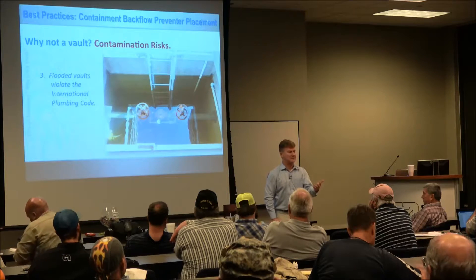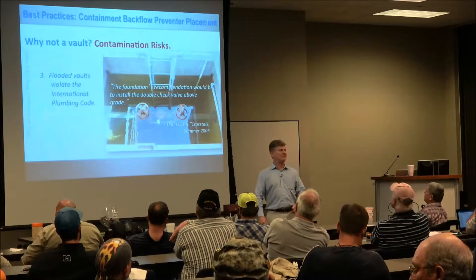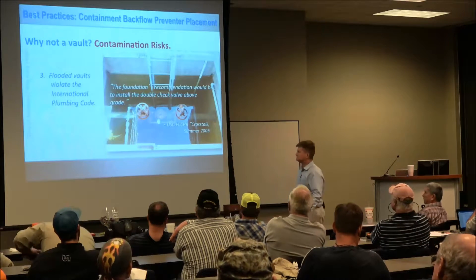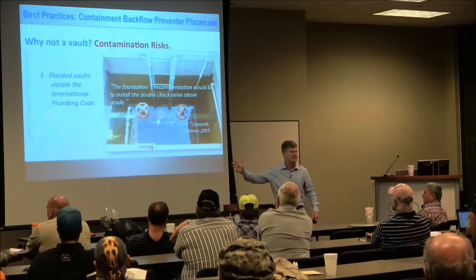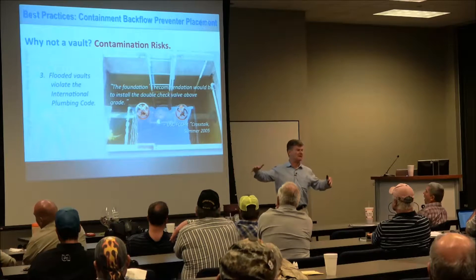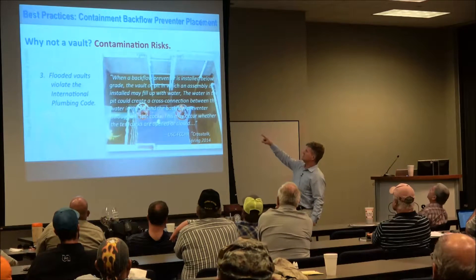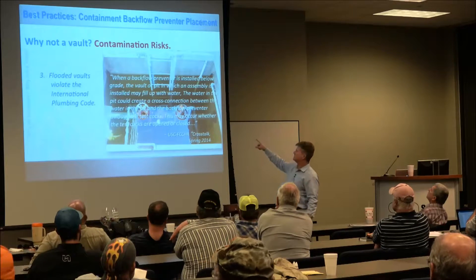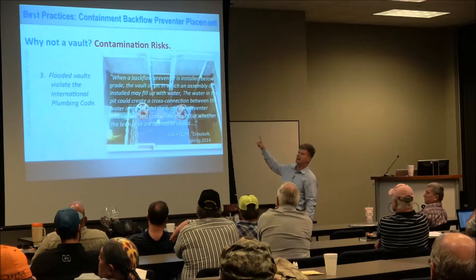We've already violated IPC in the way I look at it. Back in 2005, USC was the first to say the foundation's recommendation would be to install the double-check valve above grade. Being unsatisfied with the degree to which that advice was adopted, they published stronger language a couple of summers ago, saying: when a backflow preventer is installed below grade, the vault may fill up with water, which could create a cross-connection between the water in the pit and the backflow preventer through the test cocks. And here's the money line: this may occur whether the test cocks are opened or closed.